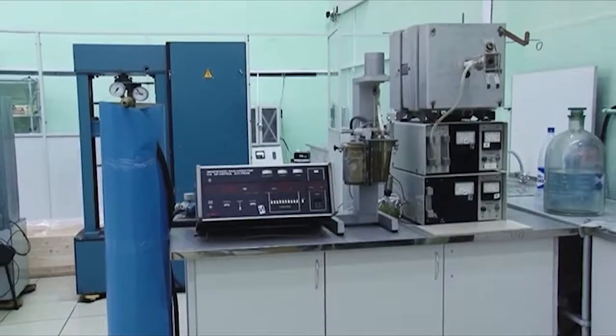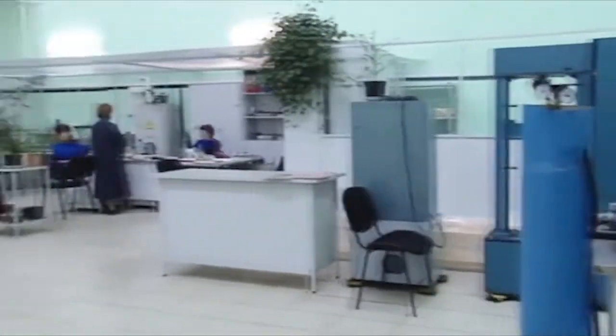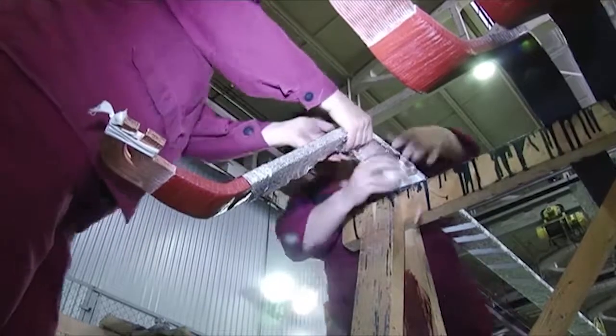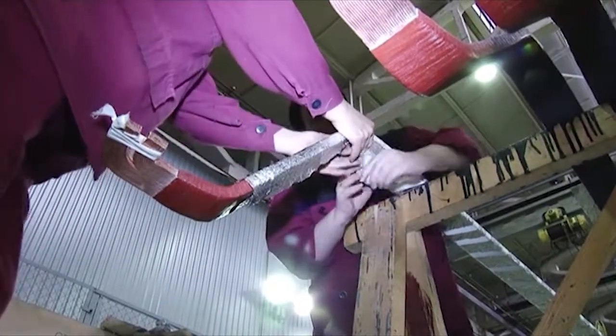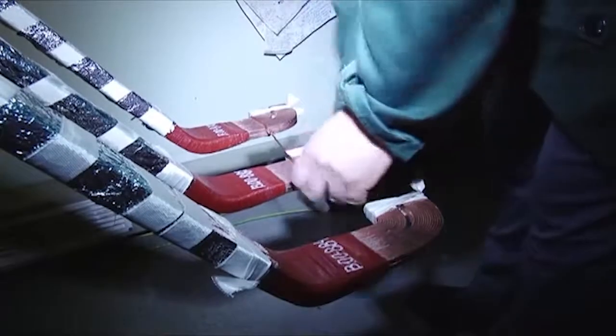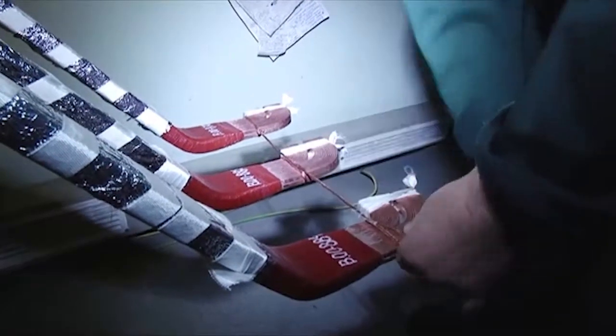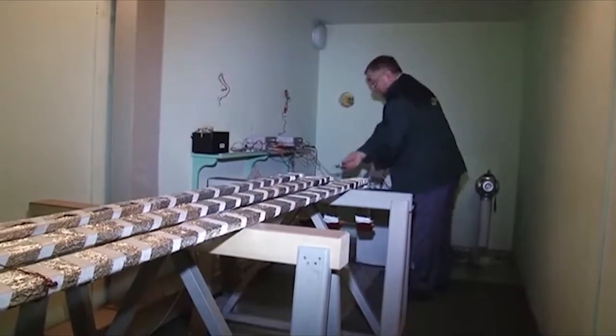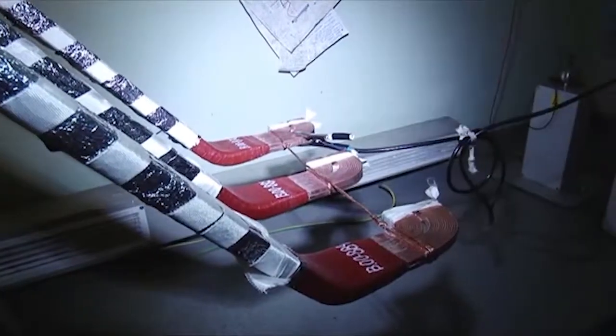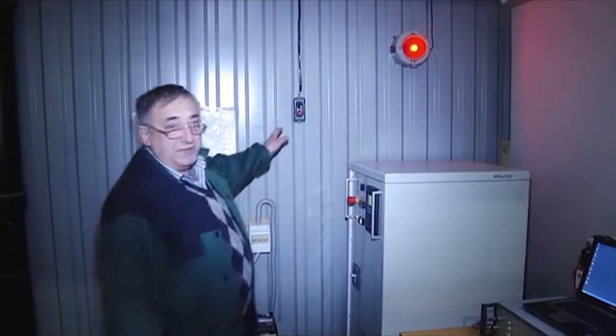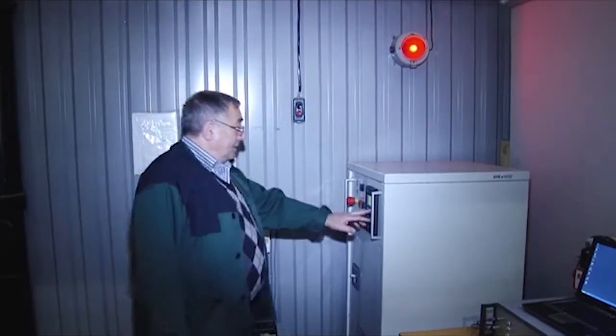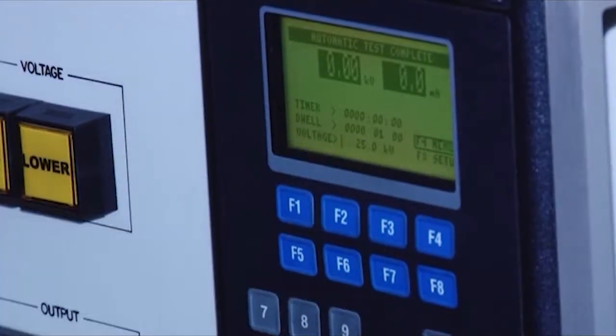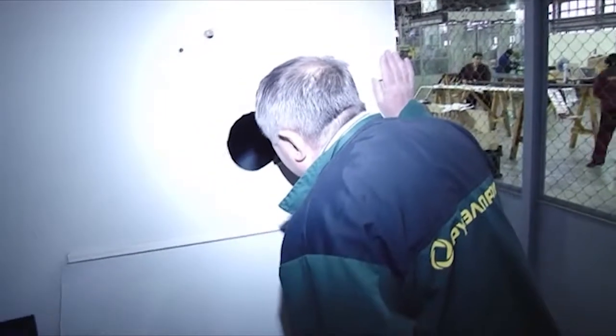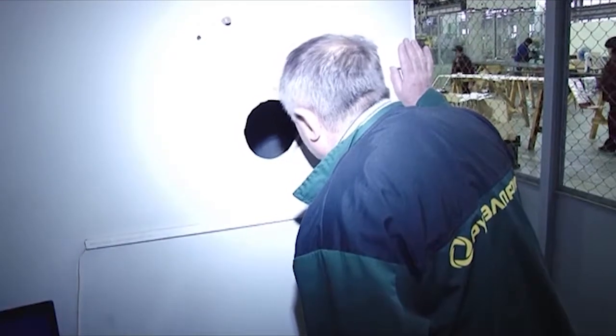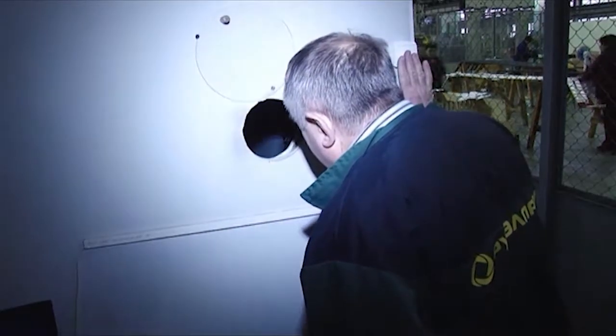Numerous tests are conducted at the enterprise in compliance with the IEC norms requirements. High voltage tests are carried out prior to finishing the bar's installation into the stator. An electrode is attached to the bars. This is then connected to the grounding strip. Then the test circuit is connected and the test voltages of 25 kilovolts and 50 kilovolts are applied to the end winding section and to the slot section correspondingly, both for 1 minute. The test samples have passed the test satisfactorily if there is no insulation breakdown.